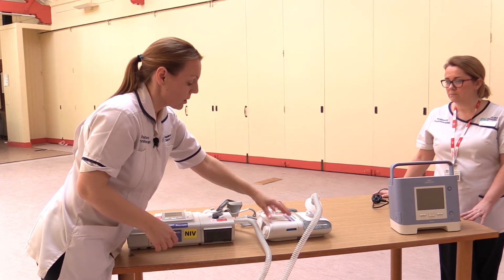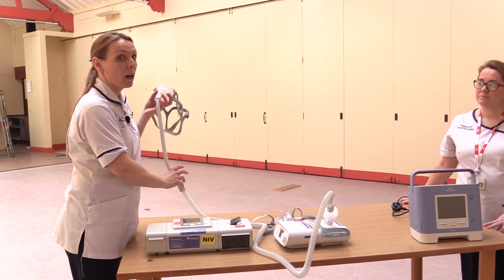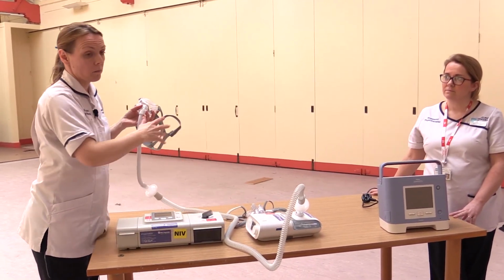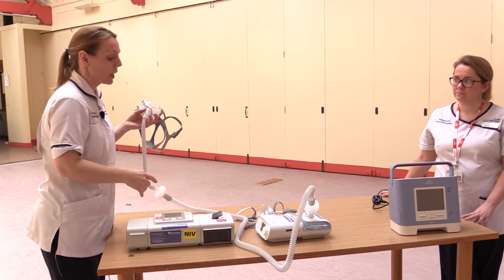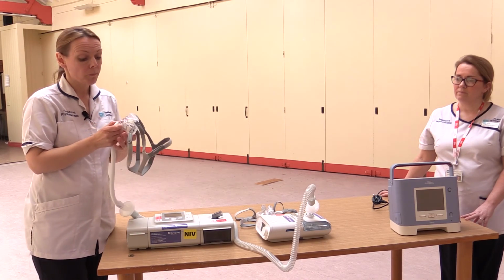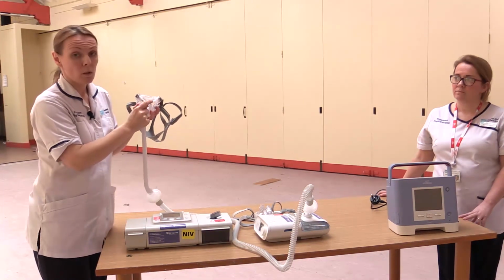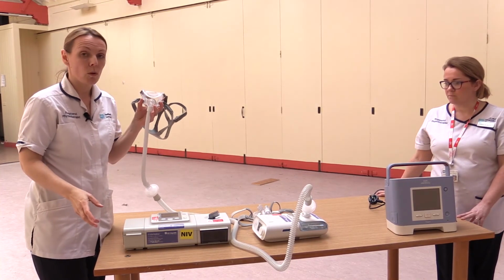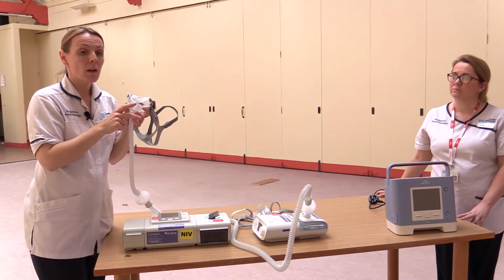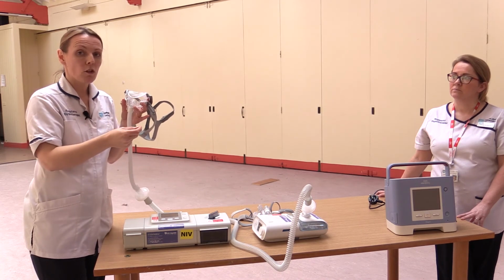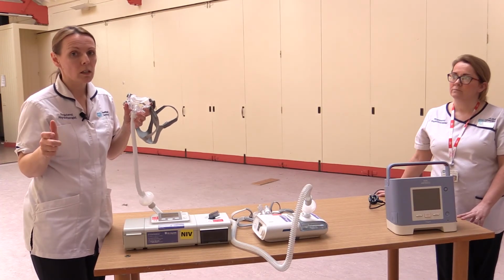So that's the most common CPAP machines that you'll see out there. In the community, you don't normally have filters because it's been provided for that particular patient, and the patients are taught how to wash out their tubing weekly and how to keep their mask clean. In the community, these masks are vented masks, so this is where the vents are in the mask, and there's no exhalation port on the system. In the hospital systems, they don't have any vents in their masks, so their masks are non-vented, but they do have an exhalation port. So a community mask does not fit with a hospital circuit, and vice versa.